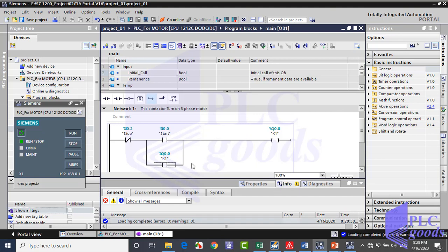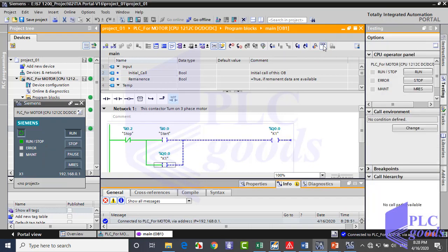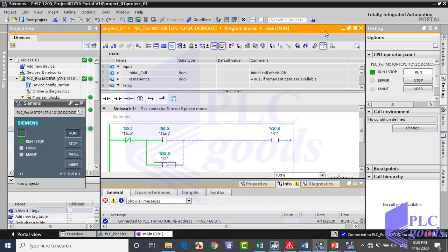I want to see my program in the PLC, not in TIA software. So click on this glasses icon. When I press this icon, TIA software shows me the PLC program which is connected to TIA. As you see, the working window is changed a little. For example, the color of this window is changed to orange color. The instructions on the right side have gone, and now a CPU is here. Or on the left, we see some green circles. To test the program, we want to change this normally open contact to close.